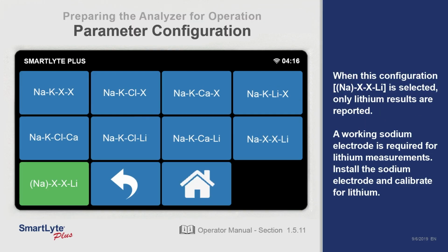When the configuration shown here on the screen is selected, only lithium results are reported. A working sodium electrode is required for the lithium measurements. Install the sodium electrode and calibrate for lithium.